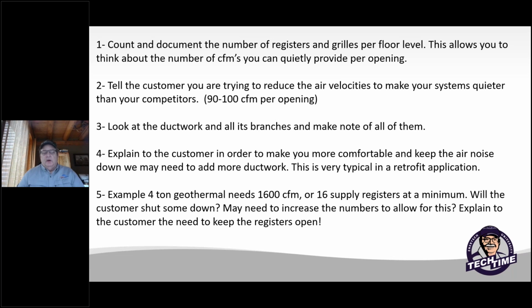If you can't do the ductwork, let's say the ductwork's in a finished basement, well, maybe we'll have to look at doing a geothermal split unit, right? So we can add it to their furnace. Again, look at the furnace model numbers, and serial numbers will actually get in there and tell you how much CFM that furnace is designed for, and then see if the ductwork can handle the amount of geothermal you can put in the match. If it can't, well, new furnace, new ductwork. But again, look at all these things and make sure you communicate to the customer.